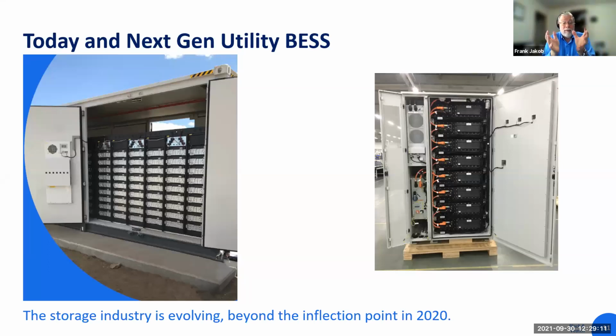Here are two pictures. On the left is what those containers with batteries inside look like. These are individual modules in racks. Each module is just like the module that might be in an electric vehicle. Nominally, each one has 20 or 30 kilowatt hours. You need 10 of them to get up to 200 or 300 kilowatt hours in a rack, and you might have 10 of those racks to put 2 megawatt hours inside a container.